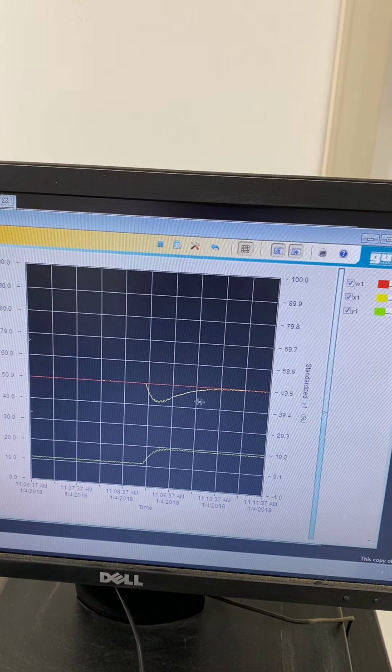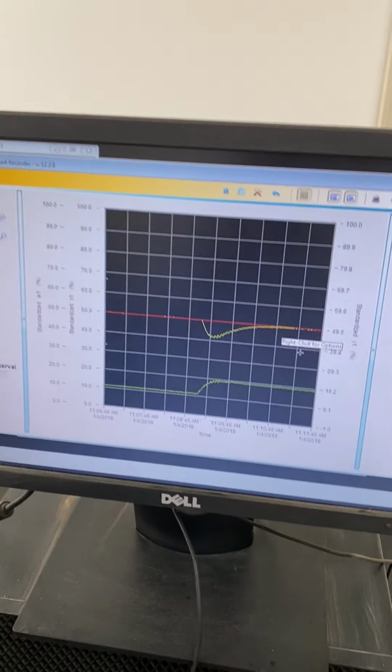Okay. So you can see right now the process value, after the drop in liquid level, is now going up, and we have now the same process value matching with the set point, but we have now a higher output signal.